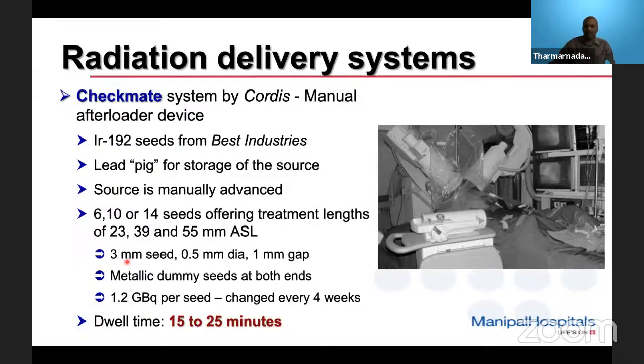Each seed was 3 millimeter in length, half a mm in diameter, and between the seeds there was a gap of 1 millimeter. Metallic dummy seeds at both ends helped in identifying the source length, and the activity was 1.2 gigabecquerel per seed. And because of the necessity to keep the dwell time or the treatment time as minimum as possible, the source had to be changed every 4 weeks.